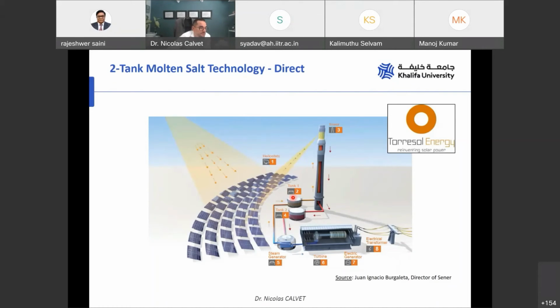So you pump the cold salt to the top of the tower to collect the heat. As the salt can go up to 600 degrees Celsius, in this case we will operate at about 575 degrees Celsius. So you pump the salt at 290, go into the solar receiver, reach 575, and bring the salt into the hot tank. At night, when you don't have sun, you pump the salt, go to the heat exchanger, produce steam for your turbine, and bring back the relatively cold salt into the cold tank, waiting for the next day's charge.